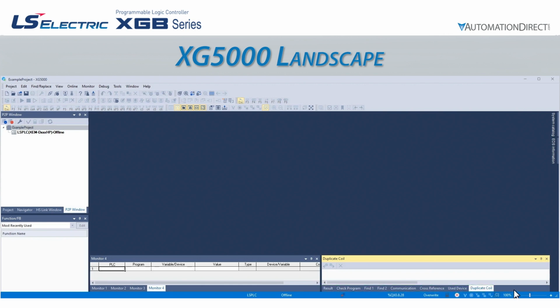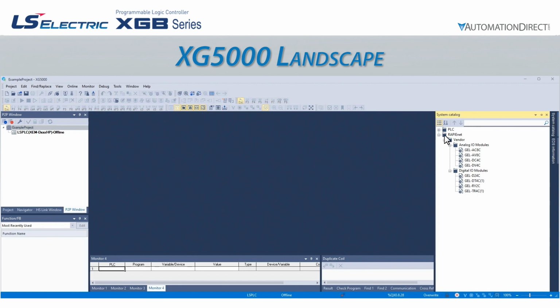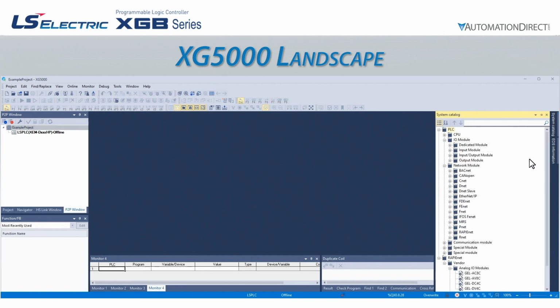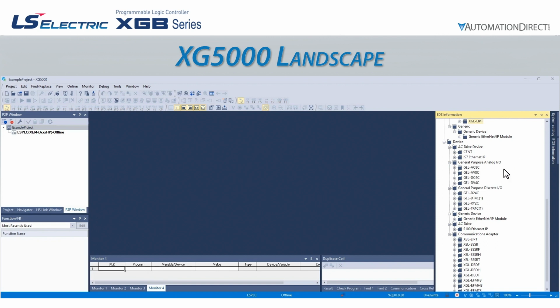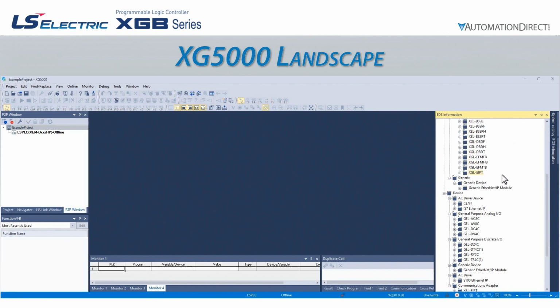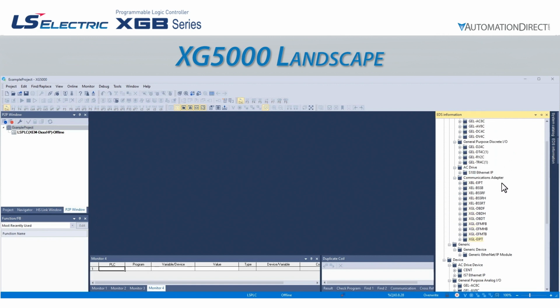To complete our tour around the screen, let's look at the small tabs on the upper right side. Here we have the system catalog and the EDS information for the project. The system catalog shows a list of all hardware compatible with the XG5000 software, and the EDS information screen displays a list of all pre-made EDS files registered with the XG5000 software. When setting up an Ethernet IP connection with a device in this list, the device's EDS file can be dragged into the Ethernet IP settings to create the configuration from this window.